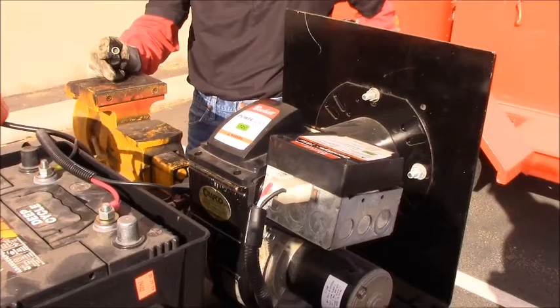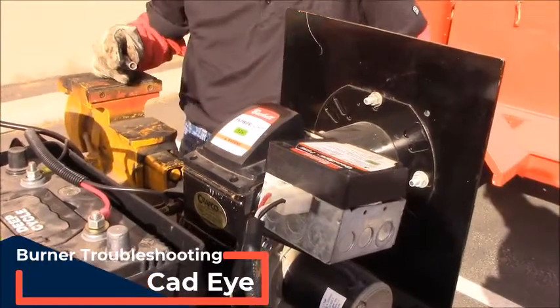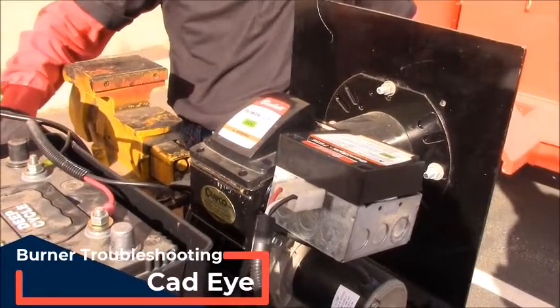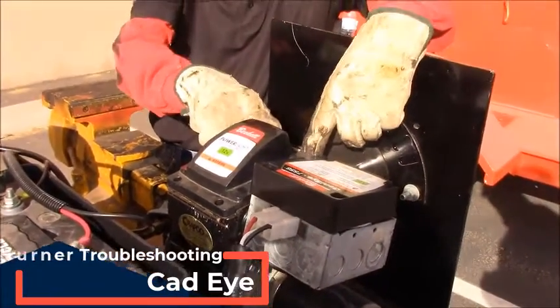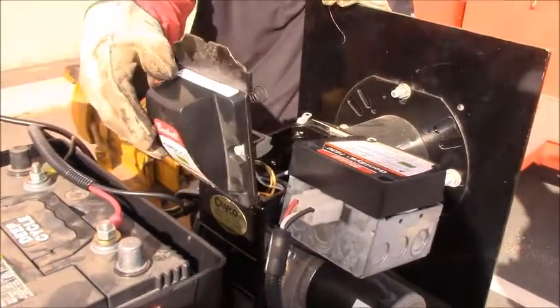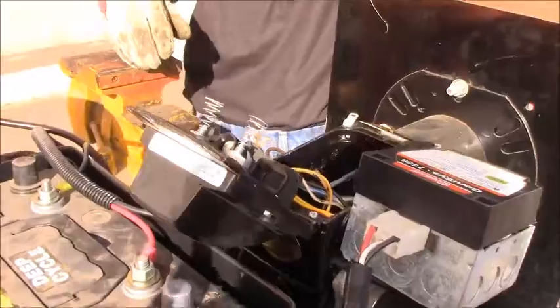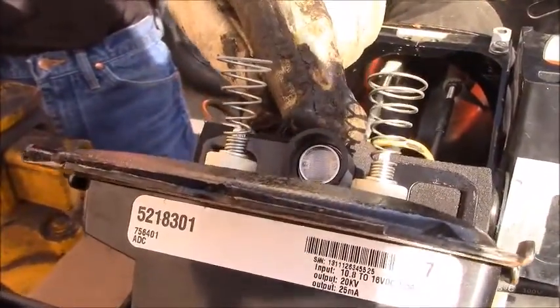On the Beckett burner, your cad eye is going to be located underneath your igniter module. First, you're going to want to loosen the screws and then move the little tabs back, and the module will hinge open. The cad eye is located right between your spring igniters.